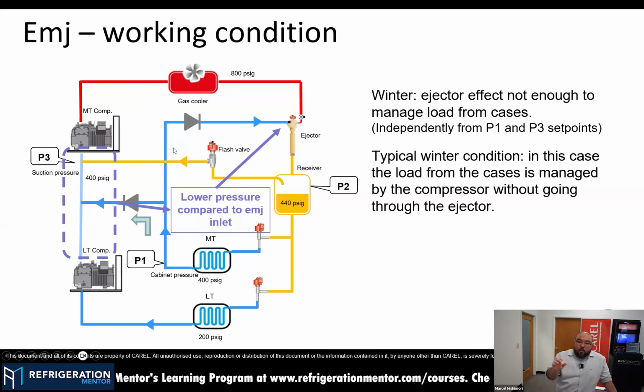So you can see that from a component perspective, adding an ejector to your system, we just need to have more pipe because we need to connect the suction line to the ejector port and two different components. No complexity here. It becomes the very same booster system that you are normally able to see in any transcritical rack. Okay.